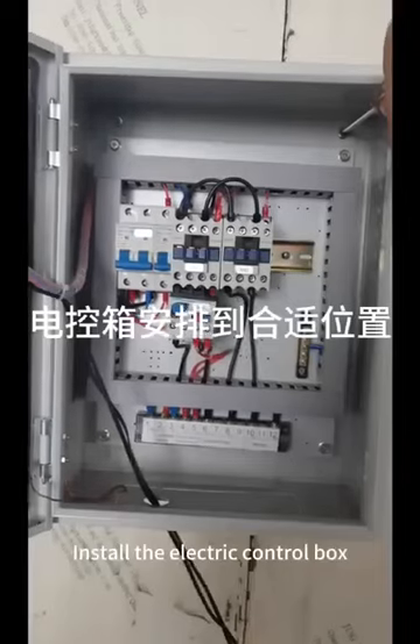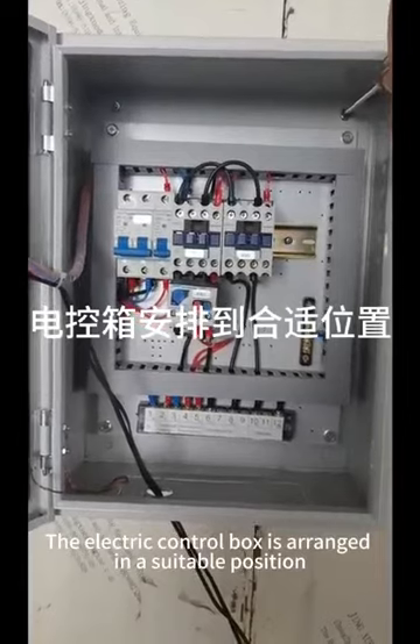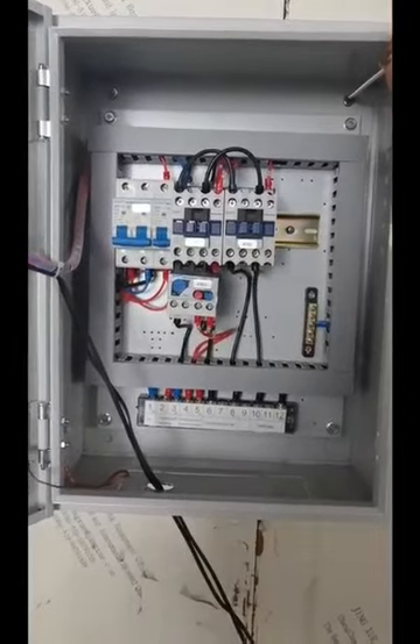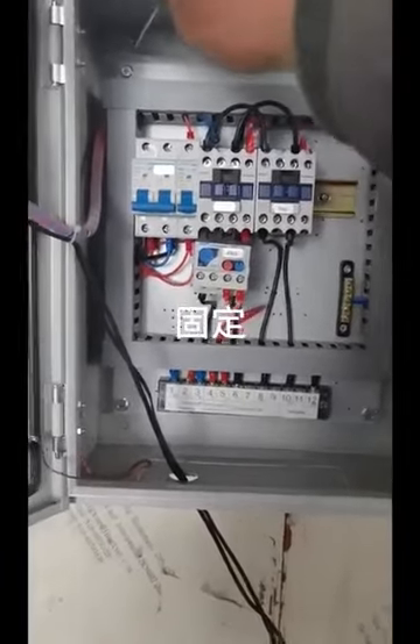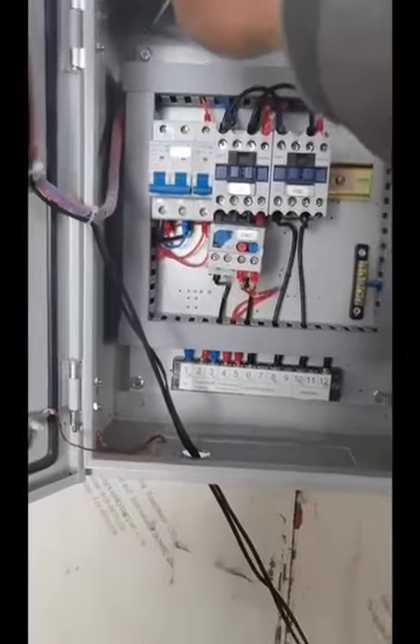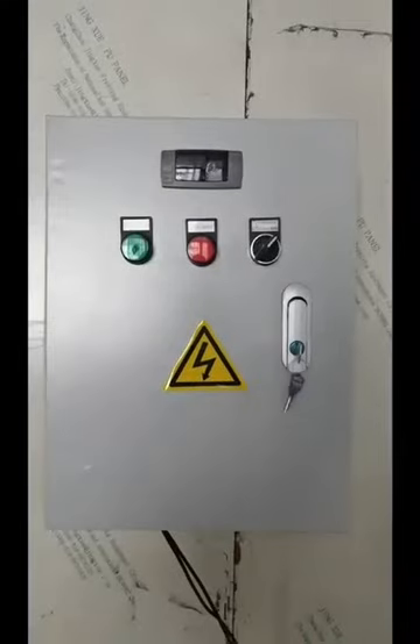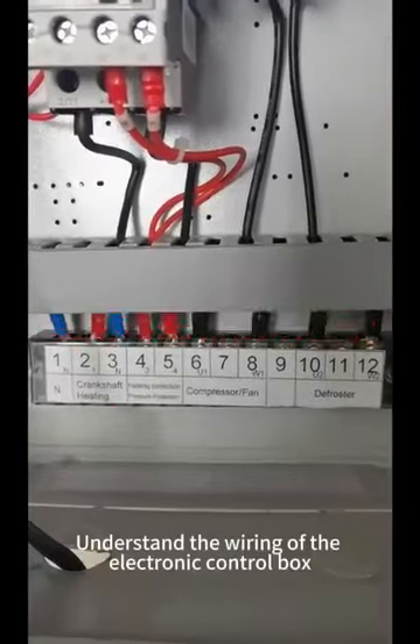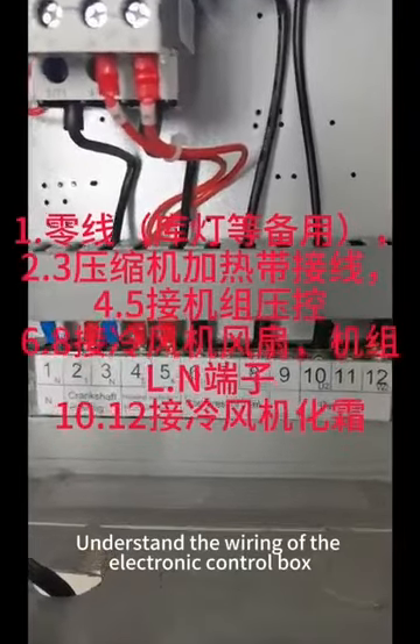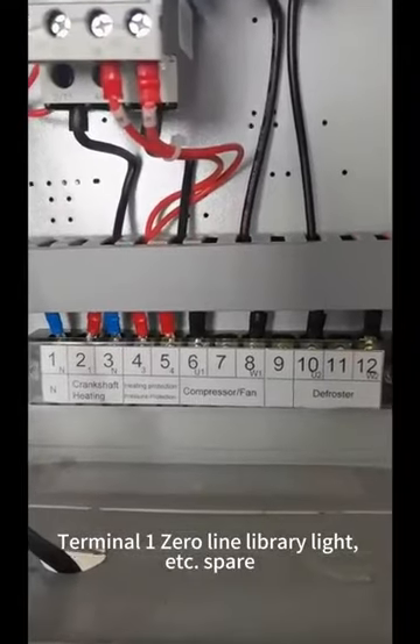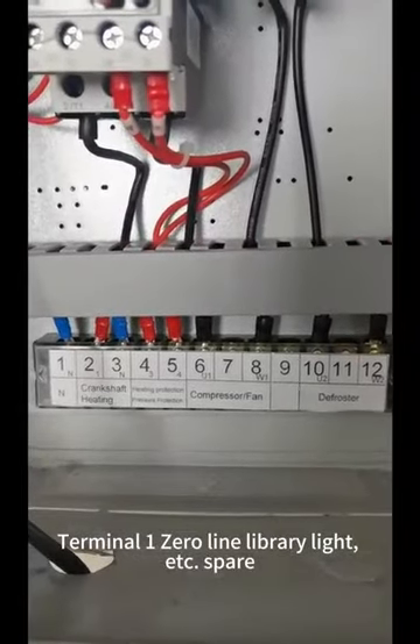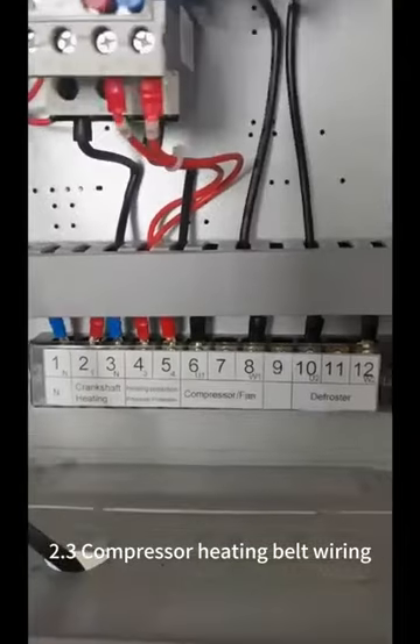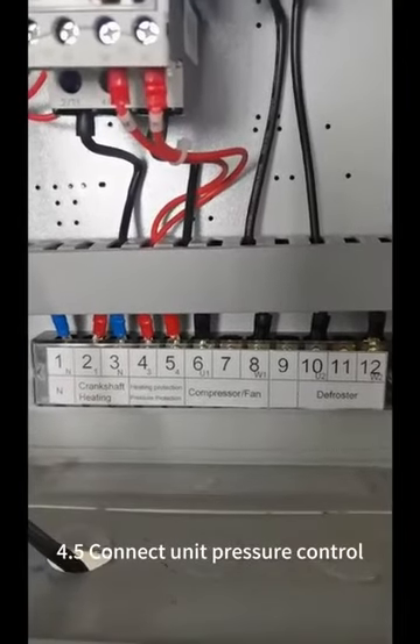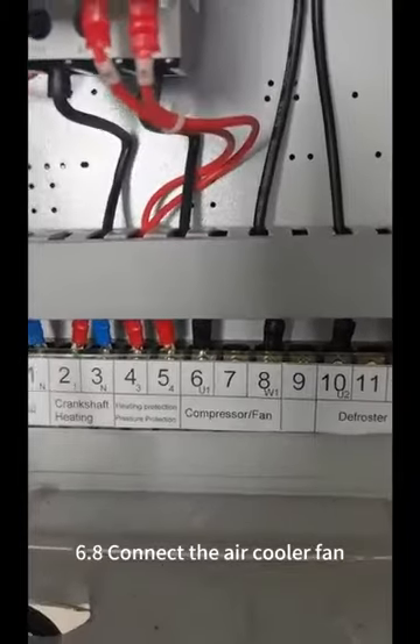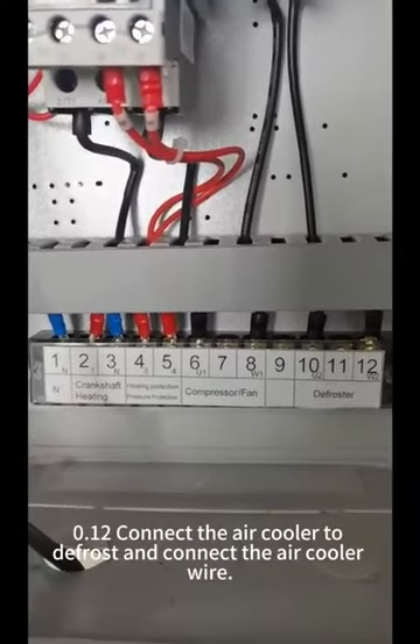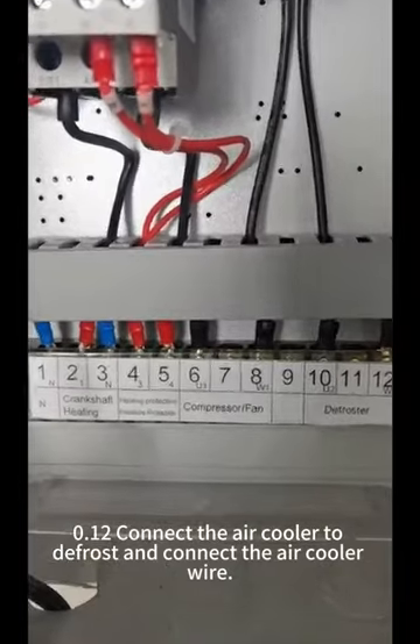Install the electric control box. The electric control box is arranged in a suitable position. Fixed. Understand the wiring of the electronic control box. Terminal 1, zero line, library light, etc., spare. 2, 3 compressor heating belt wiring, 4, 5 connect unit pressure control, 6, 8 connect the air cooler fan, 10, 12 connect the air cooler defrost and connect the air cooler wire.